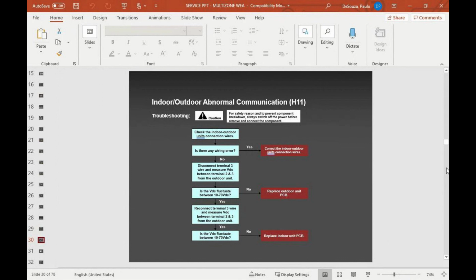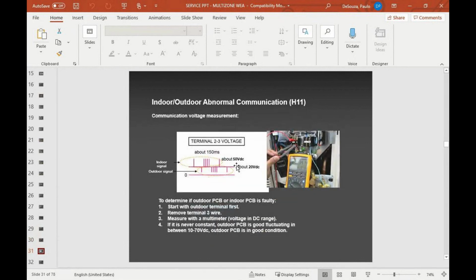I have come across this error code on brand new installs, and in most cases, it was the control wire issue. Some guys may have crossed the 1 and 2 or the 2 and 3, and this problem happened. Another time, a condensate pump was used, and they broke the number 3 wire. Please don't break number 3 wire. If you want to break any wire, break number 1. That's the line 1. Don't break number 2, because number 2 behaves as a common wire to number 3 and number 1. So if you have a condensate pump, and if it's calling for safety, to shut down the unit in safety, break number 1 wire.